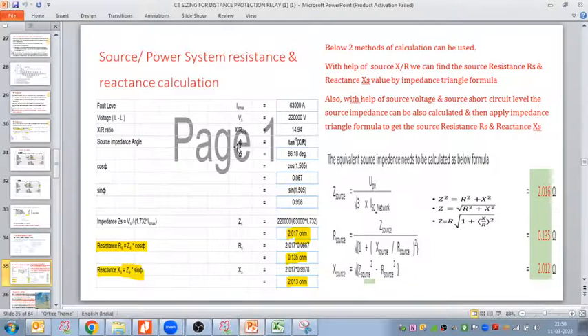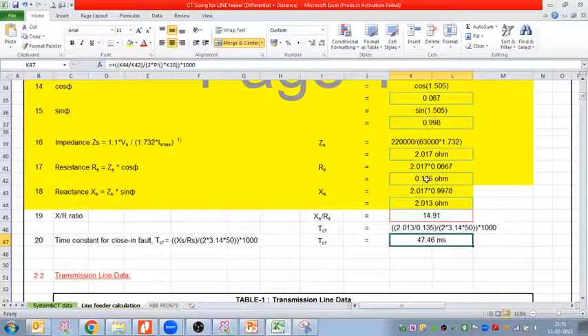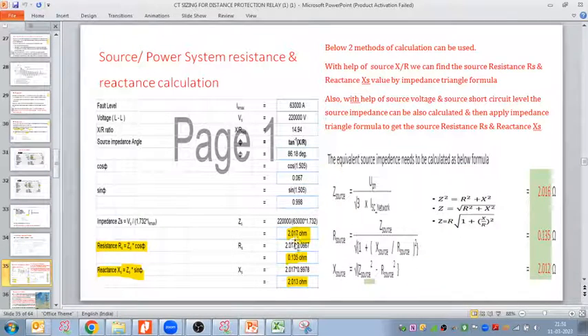The other approach we can follow uses the same formula: source impedance Z source equals the voltage divided by root 3 into ISC. With this formula we can find the source impedance. Again, 220 kV divided by root 3 into 63 kA gives a source impedance of 2.016, which is similar to the 2.017 we got here. So by this formula and that formula, the result is about the same.